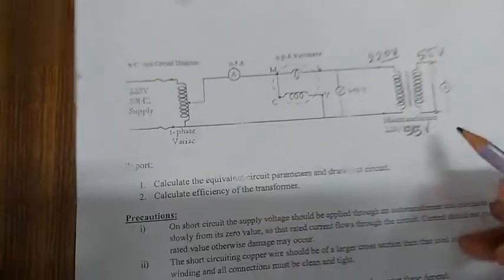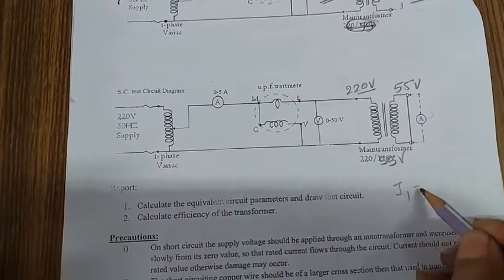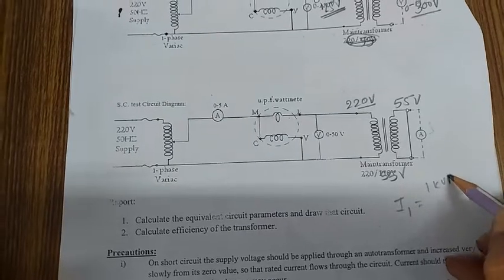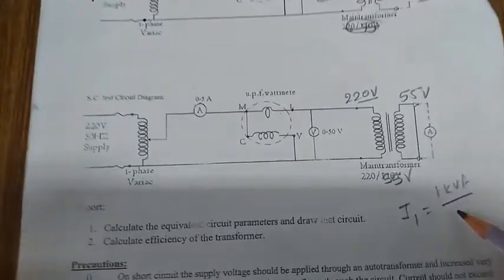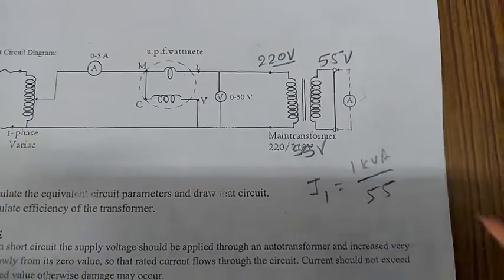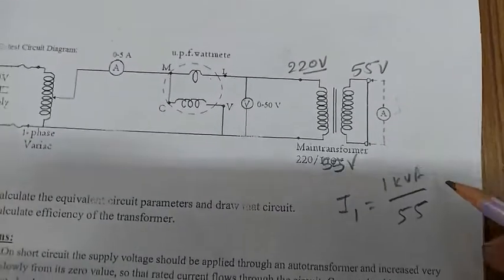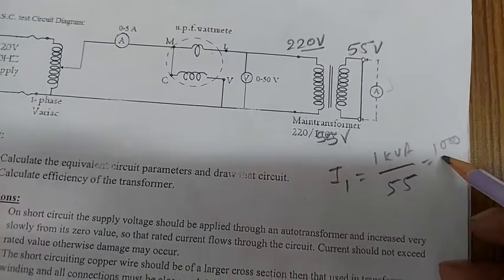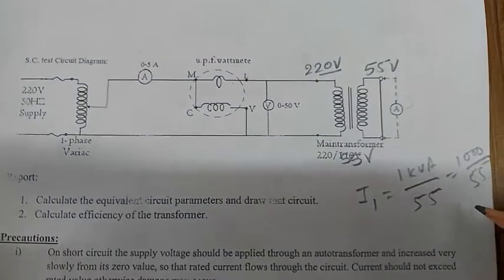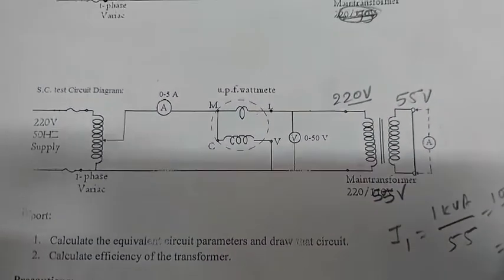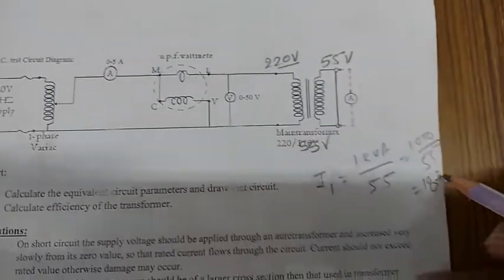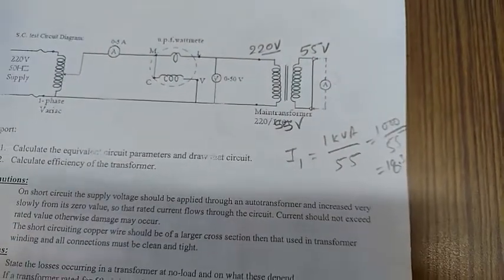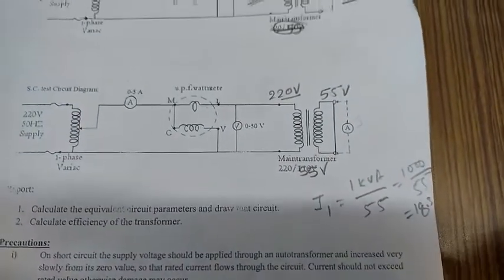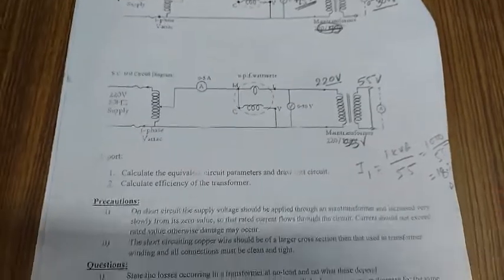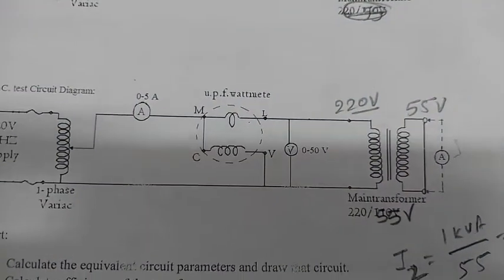And as for the transformer specification, the short circuit current can be calculated from the kVA rating. The kVA rating is 1 kilovolt ampere. So 1 kilovolt ampere should be divided by 55, because the secondary side is the 55 volt side. So automatically we will get 18.18, or say 18 ampere. That current is called the full load secondary current.